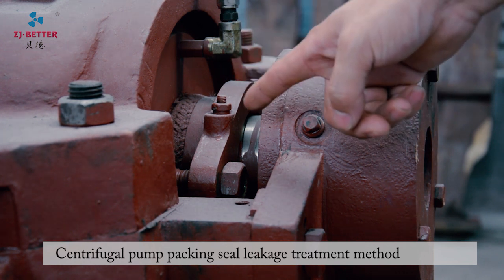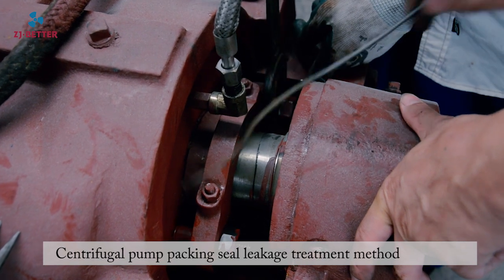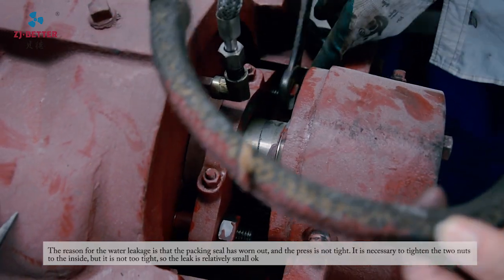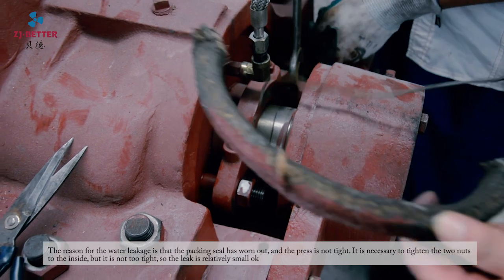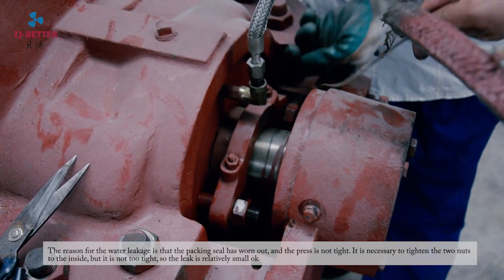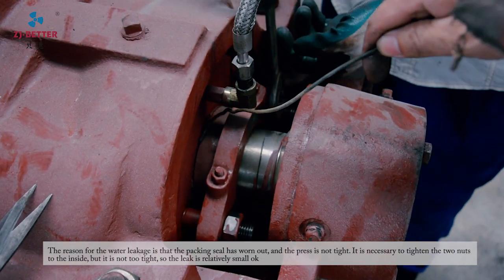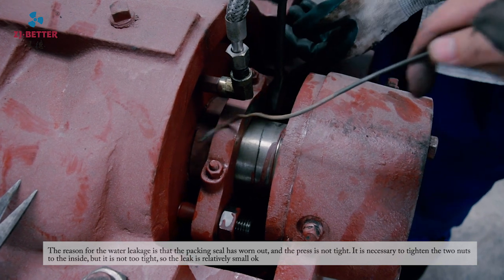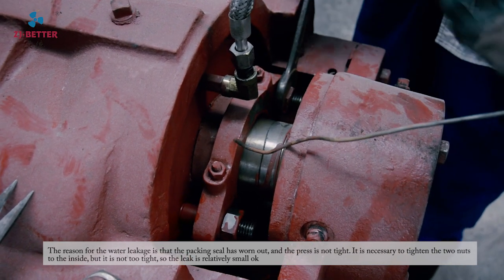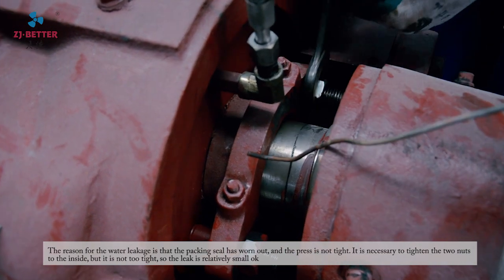Centrifugal Pump Packing Seal Leakage Treatment Method. The reason for the water leakage is that the packing seal has worn out and the press is not tight. It is necessary to tighten the two nuts inward, but not too tight, so the leak will be relatively small.